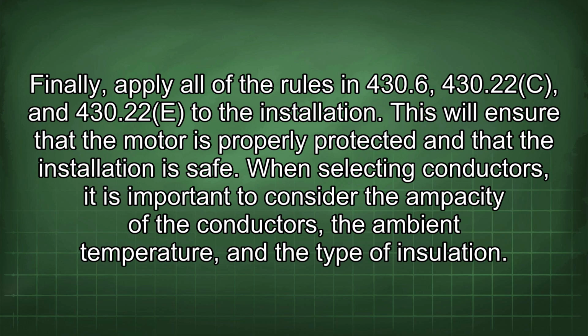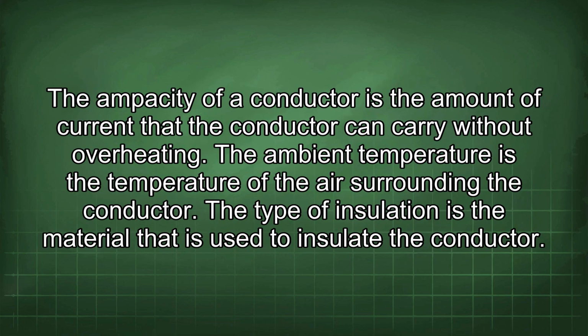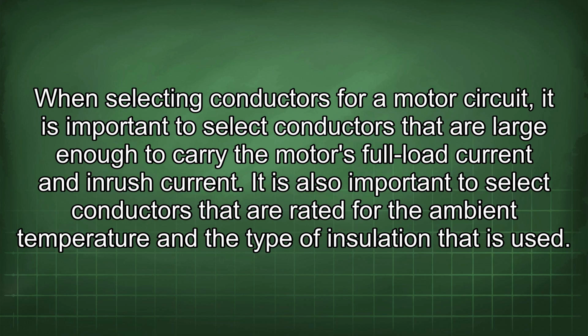When selecting conductors, it is important to consider the ampacity of the conductors, the ambient temperature, and the type of insulation. The ampacity of a conductor is the amount of current that the conductor can carry without overheating. The ambient temperature is the temperature of the air surrounding the conductor. The type of insulation is the material that is used to insulate the conductor. When selecting conductors for a motor circuit, it is important to select conductors that are large enough to carry the motor's full load current and inrush current. It is also important to select conductors that are rated for the ambient temperature and the type of insulation that is used.